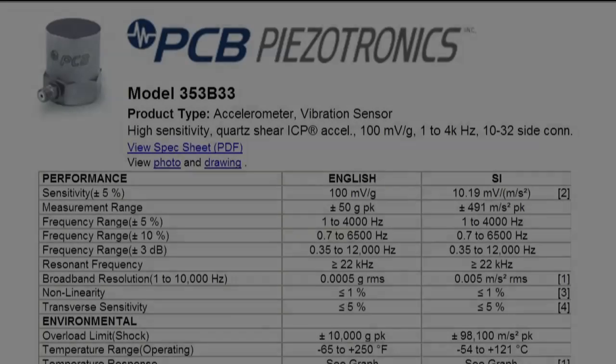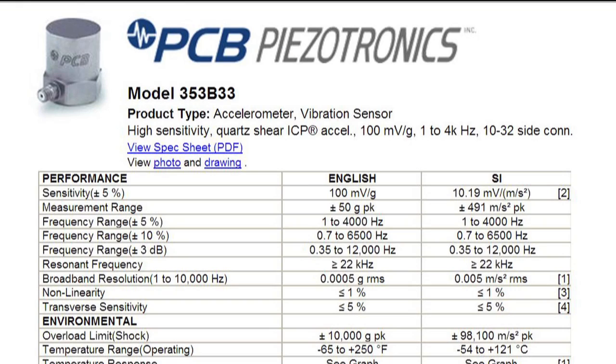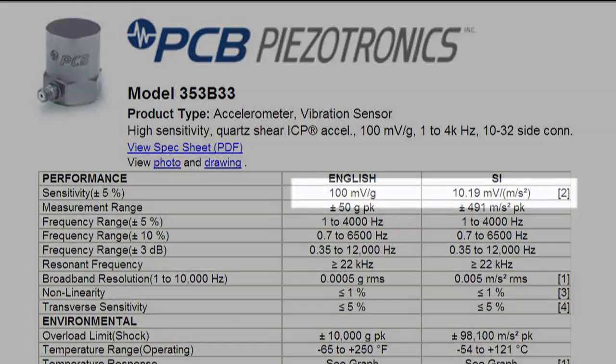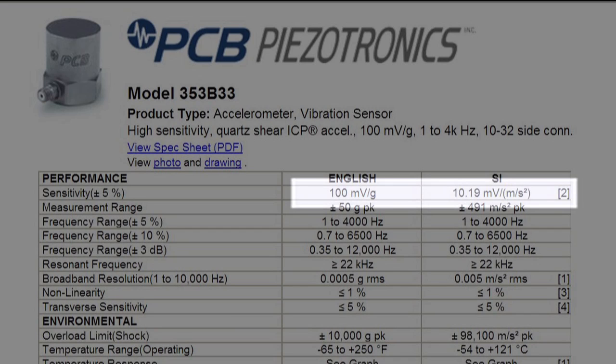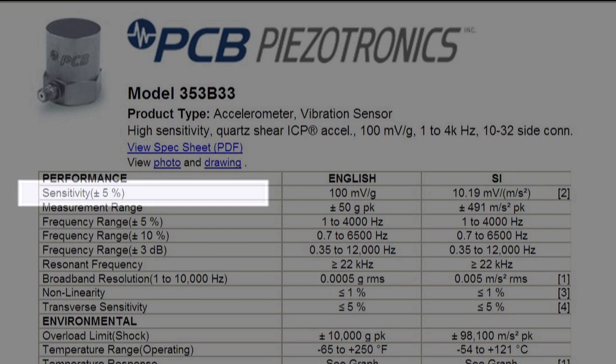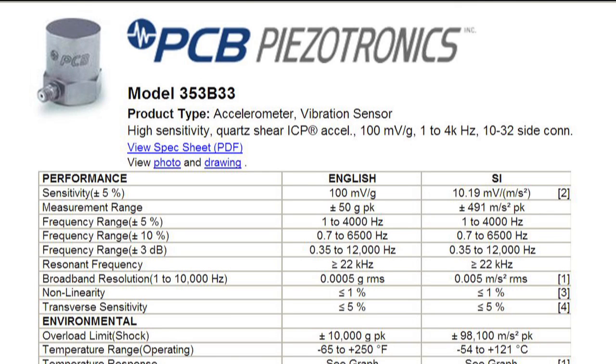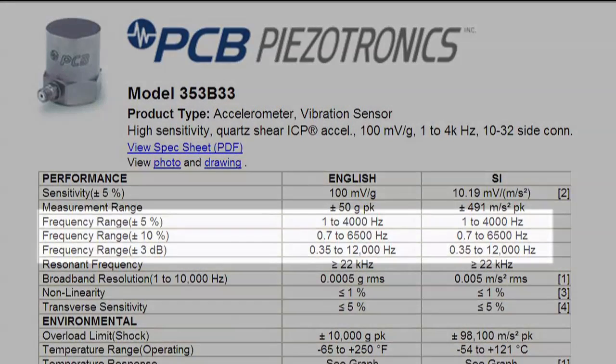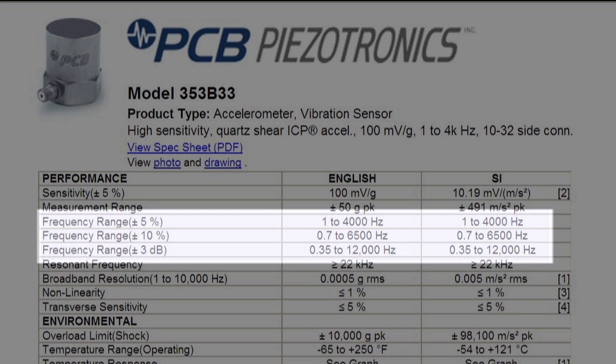A sensor specification will state the nominal sensitivity of the sensor along with the allowable deviation from this sensitivity. The nominal sensitivity is defined at a specific frequency referred to as the reference frequency. The frequency response of an ideal vibration sensor is a flat, straight line. The frequency response of an actual vibration sensor, however, deviates from this.